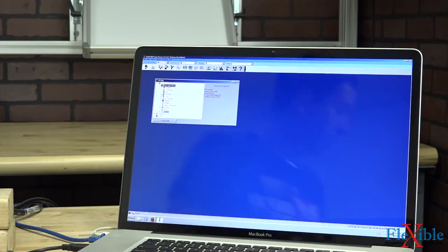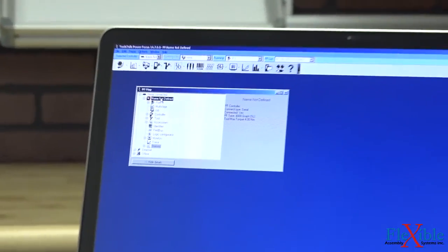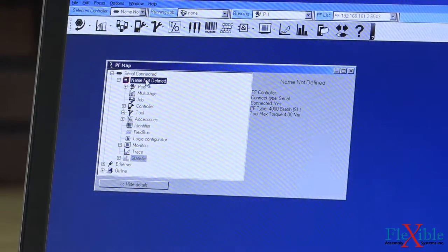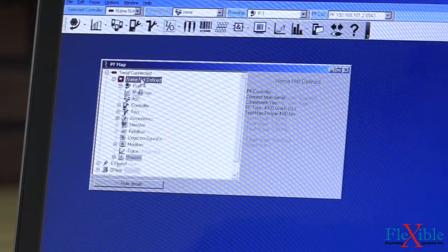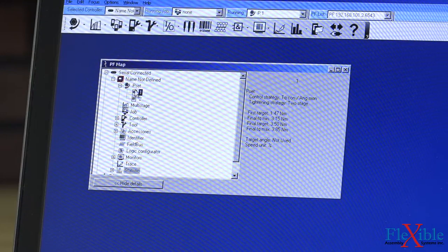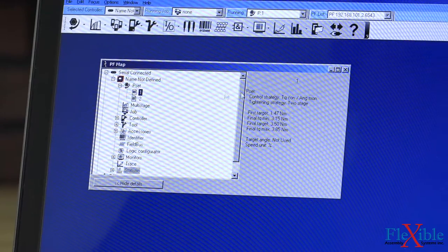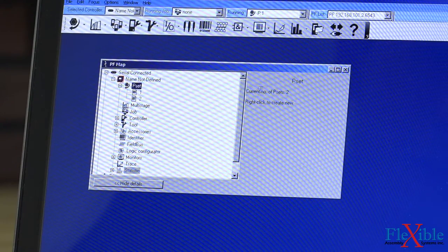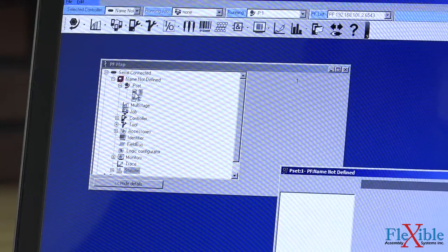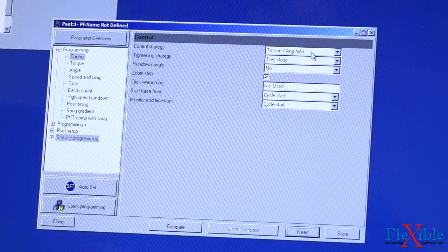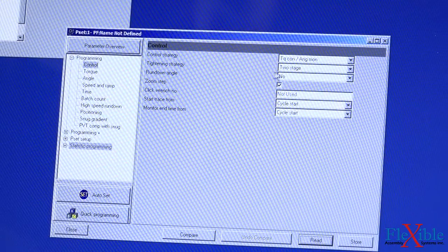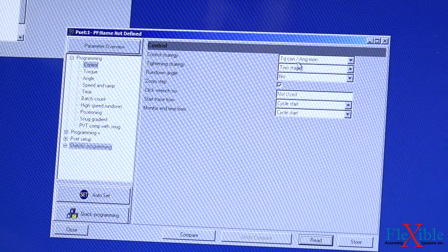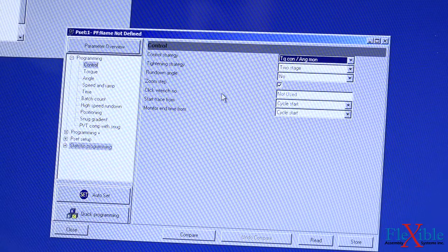Now that it's finished connecting, we could see that we have all of our options to set P-Sets, view all the jobs and such. As you can see here, we have a couple P-Sets in our P-Set menu. Just one and two. If we wanted to, we could right click on the P-Set itself to create a new one. But I'm going to edit P-Set number one. I'll double click on it to open it up. Now our P-Set window opens up and we have a few different control options. We're going to use a two-stage tightening strategy as well as doing torque control with just angle monitoring. Something simple.